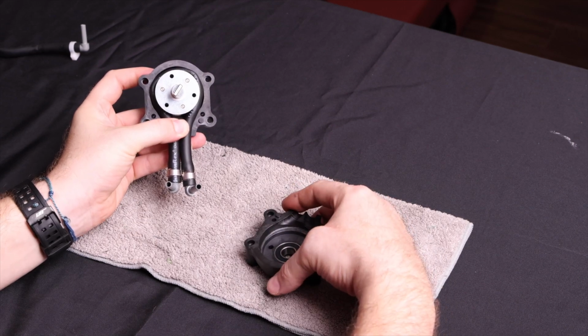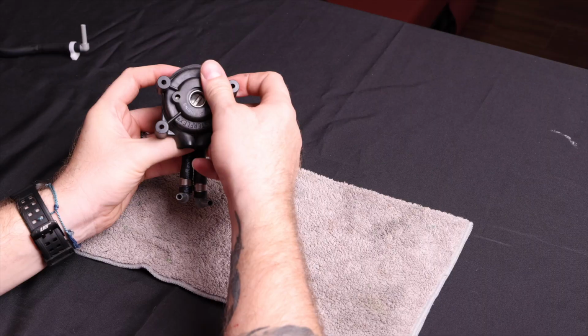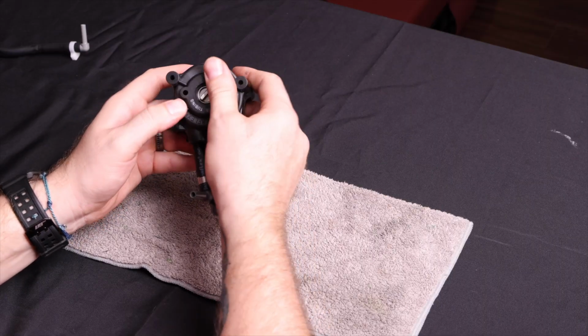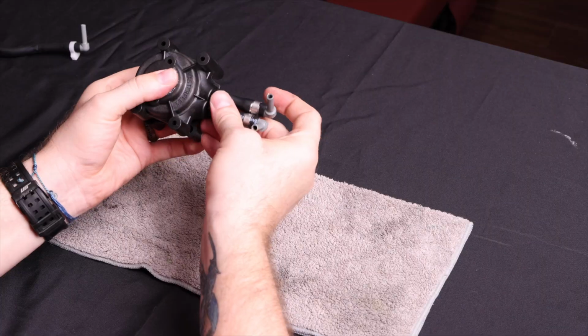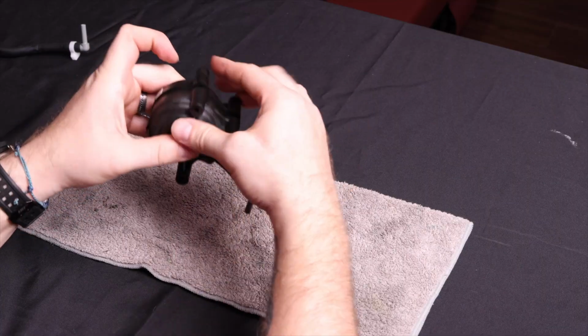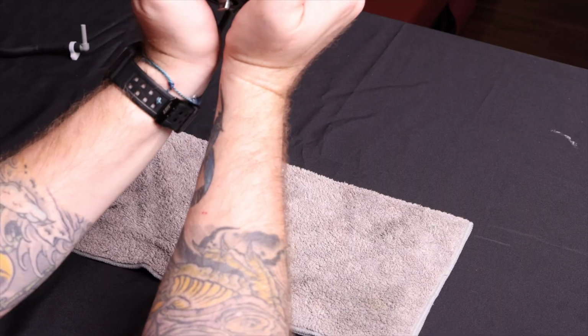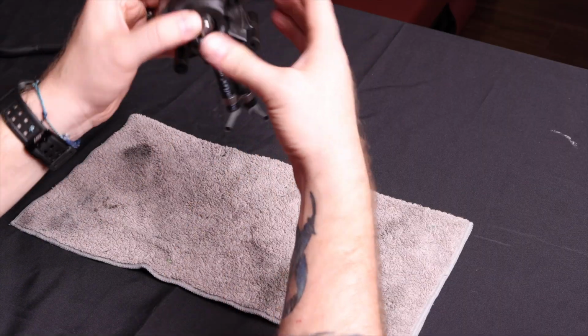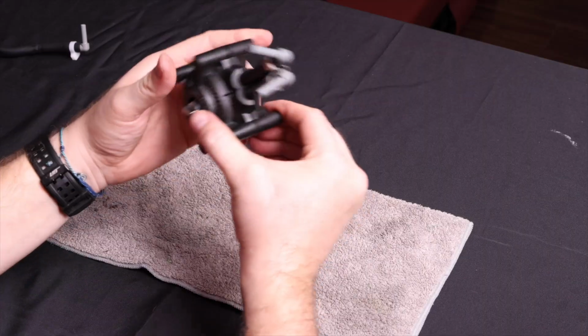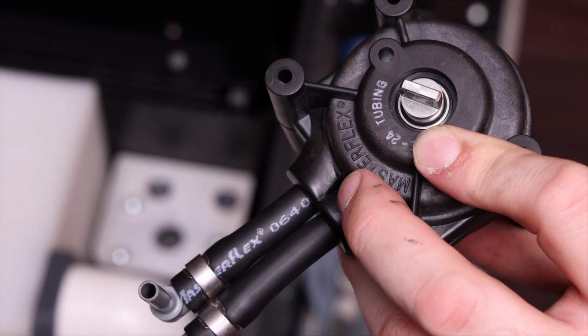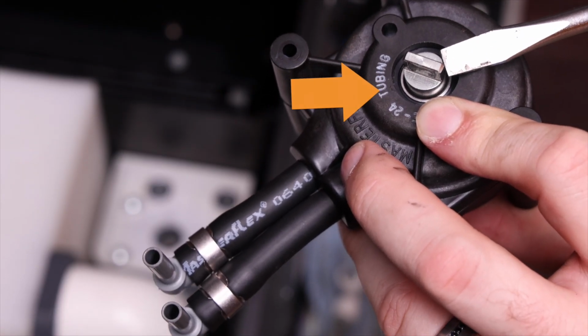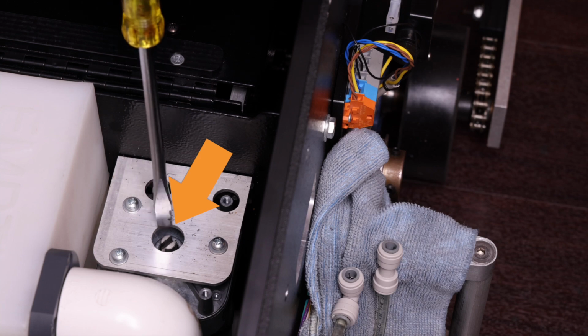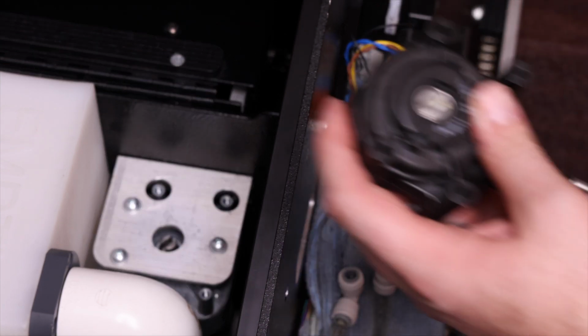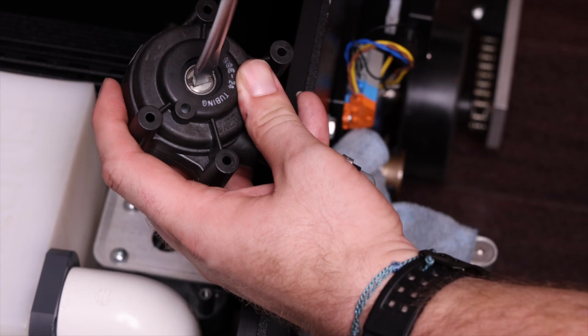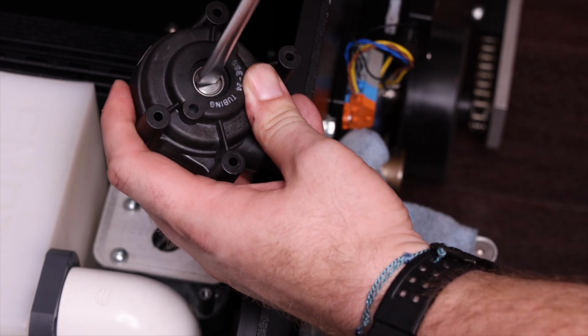Once complete, take the lower bell, slide it over the shaft, making sure our tube stays in the groove. And gently squeeze shut. Before reinstallation, we will want to make sure our bearing shaft is in line with our motor shaft. If not in line, use a flathead screwdriver and turn the bearing shaft until in line.